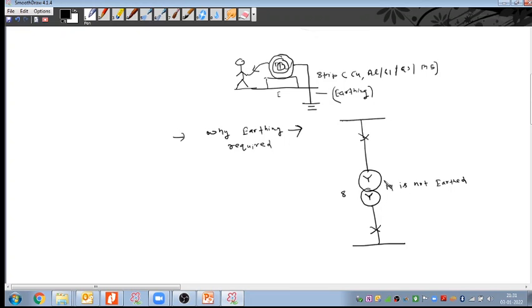First of all, if any line to ground fault happens, the fault is there, but it cannot be sensed. Why can it not be sensed? Because there is no return path for this fault current. So this is problem number one: the ground fault cannot be sensed. Second problem: since this is a star connection, in a star connection the voltage on the phase is the line to line voltage divided by root 3. This will be the phase voltage. Suppose this is a 33 by 11 kilovolt transformer.